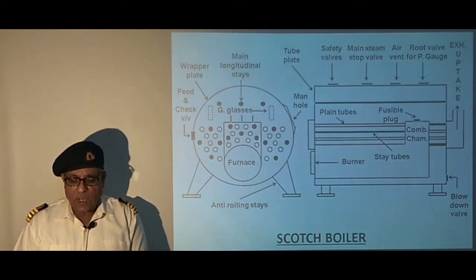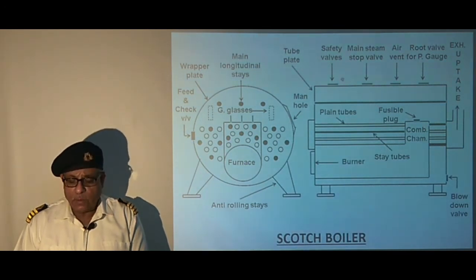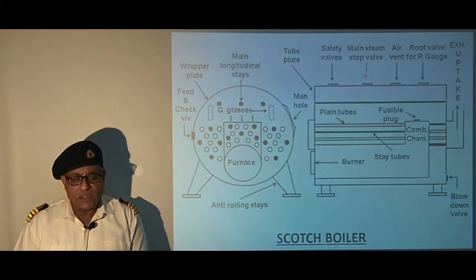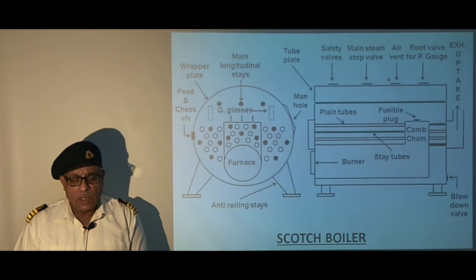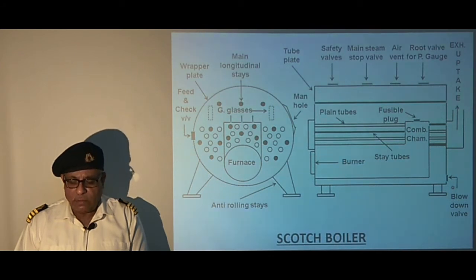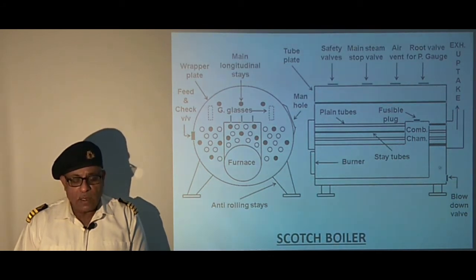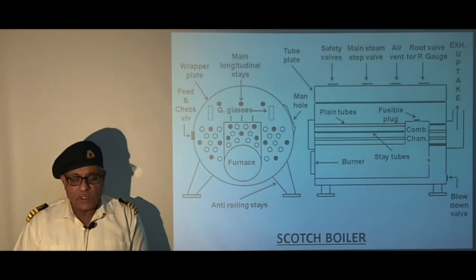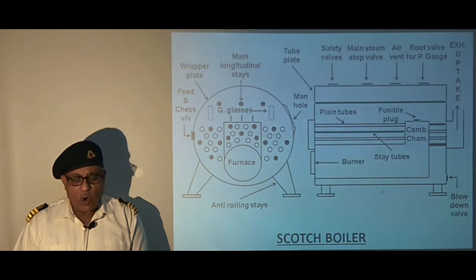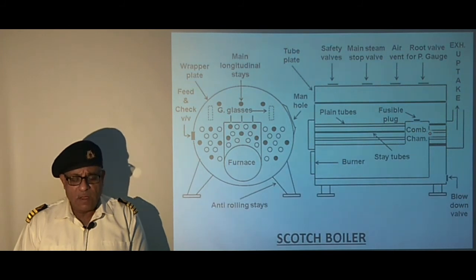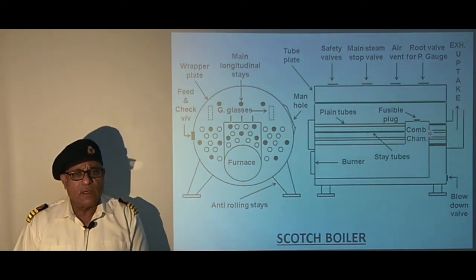Important boiler mountings include the safety valve, main steam stop valve, air vent, feed and check valve, manhole, blow down valve, and the fusible plug, which is fitted on older type boilers. In modern boilers, instead of a fusible plug there is a low water level trip device, which is a better arrangement.